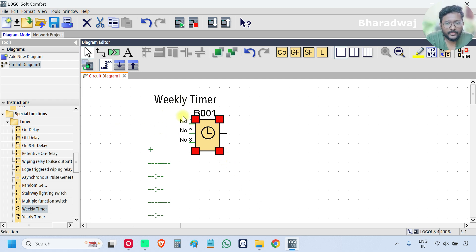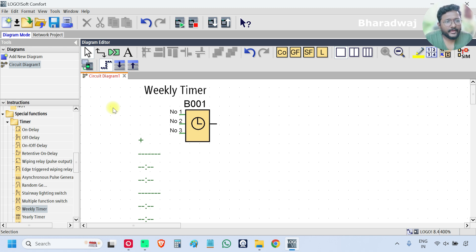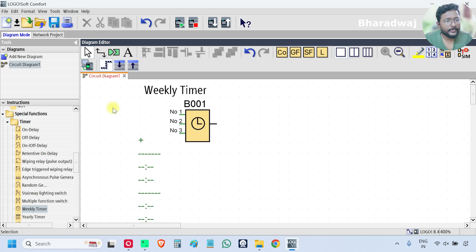If you see, there are no inputs, only one output, and we can enter three conditions. What this Weekly Timer does is: whenever you want to turn on an output at a specific day and specific time — I mean real time — you can use this Weekly Timer block to turn on or turn off an output. One thing to remember: the PLC must have an inbuilt real time clock.